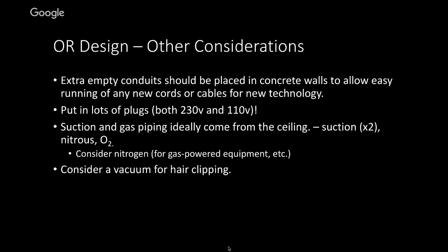Put in lots of plugs. If you're going to be dependent on equipment coming from World Medical Mission or from North America, make sure you've figured out a system allowing both 110 and 230 volt. It's actually cheaper to change the plugs than to risk someone plugging the wrong thing into the wrong voltage and frying it. So if you have two different voltages for equipment, have two different plugs.